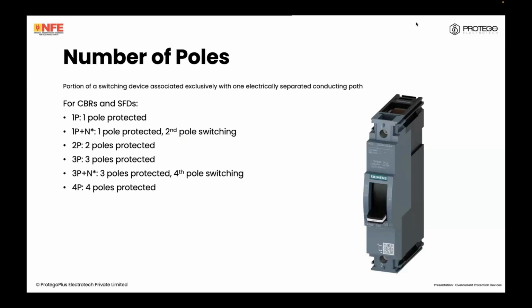Okay. Will do. So these one pole plus, like I said, so that you got one pole plus neutral. When you've got two pole devices, this means both poles are protected. So this would be a two pole breaker. Three poles would mean all three poles are protected. Three pole plus neutral is you've got three poles protected and the fourth pole is switching. Similar story like the one pole plus neutral. And the four pole is four poles protected, including the neutral.